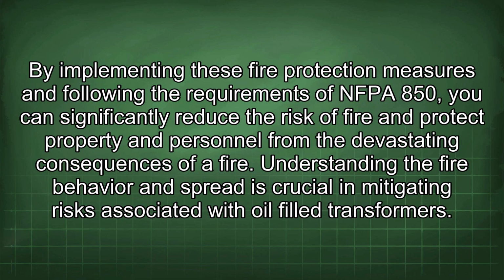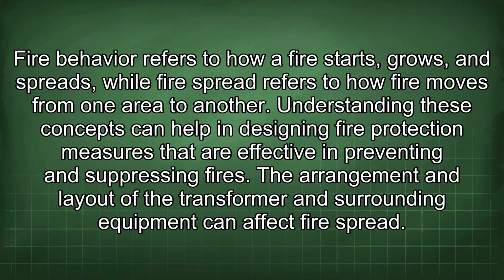By implementing these fire protection measures and following the requirements of NFPA 850, you can significantly reduce the risk of fire and protect property and personnel from the devastating consequences of a fire. Understanding the fire behavior and spread is crucial in mitigating risks associated with oil-filled transformers.